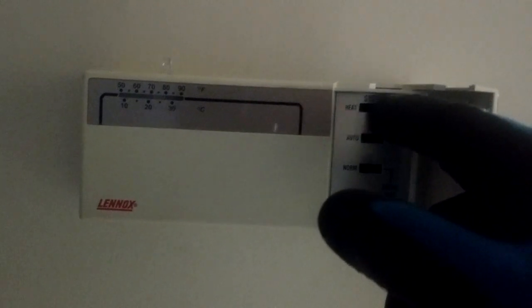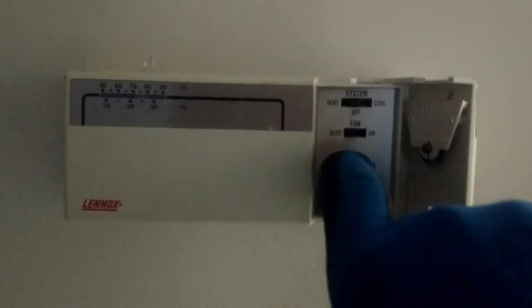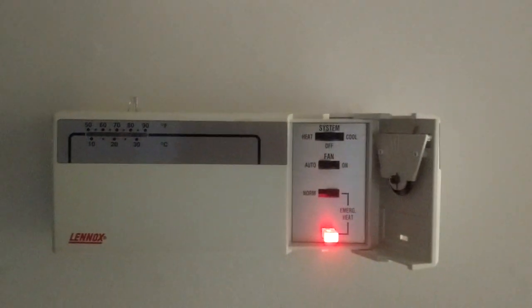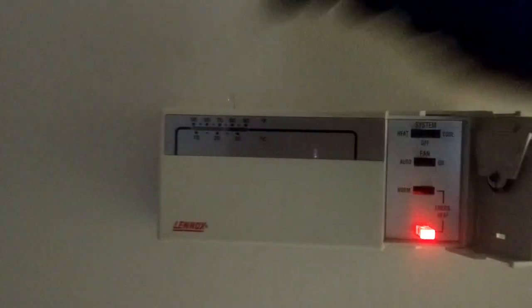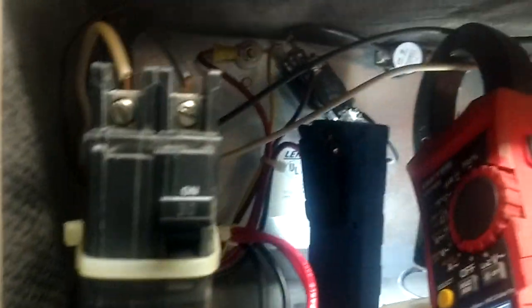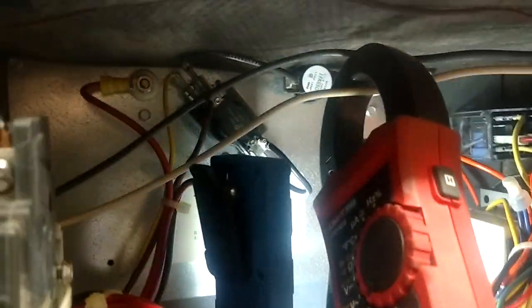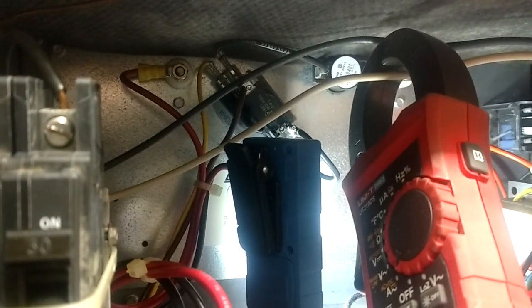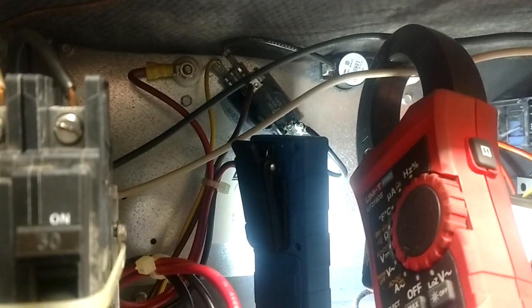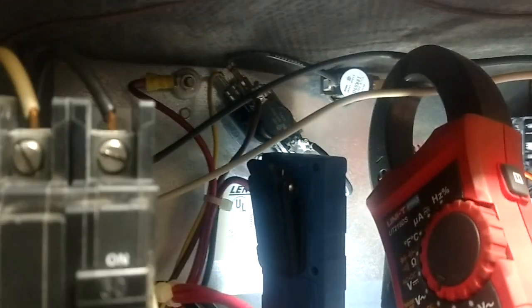And now we're going to go back to our emergency heat setting. We're going to go back to heat with the temperature up, and we're going to check that blower through the sequencer back there in the back. We're going to let that sequencer warm up and time out. There we go. There's the blower.